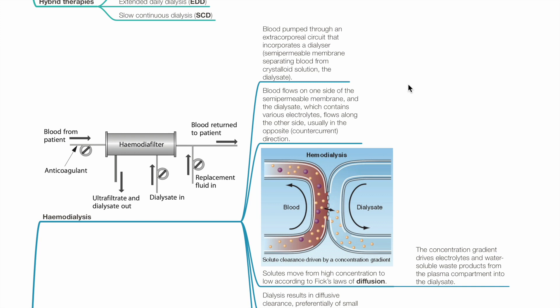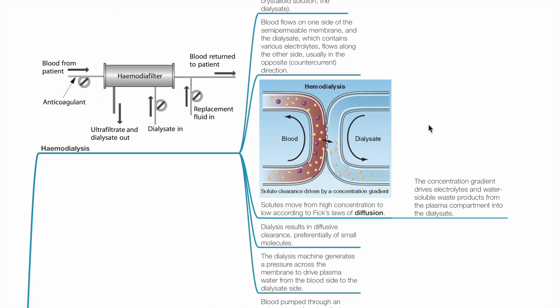Blood flows on one side of the semi-permeable membrane, and the dialysate, which contains various electrolytes, flows along the other side, usually in the opposite or counter-current direction. Solutes move from high concentration to low concentration according to Fick's law of diffusion. The concentration gradient drives electrolytes and water-soluble waste products from the plasma compartment into the dialysate. Dialysis results in diffusive clearance, preferentially of small molecules.